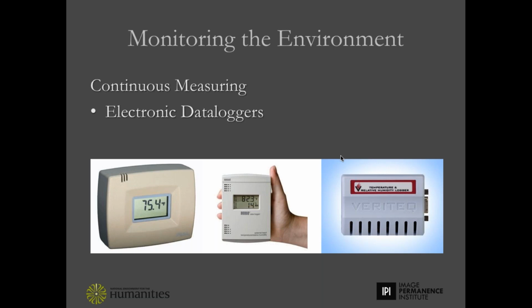So depending on the construction of your building, you may or may not be able to use wireless loggers. I know a lot of people are interested in wireless loggers because you don't have to manually download the data, but it really depends on your building construction. Concrete and steel frame construction, usually the wireless signal can't actually get through. So this is something to really investigate thoroughly before you purchase wireless.